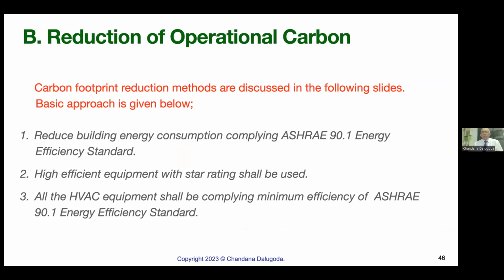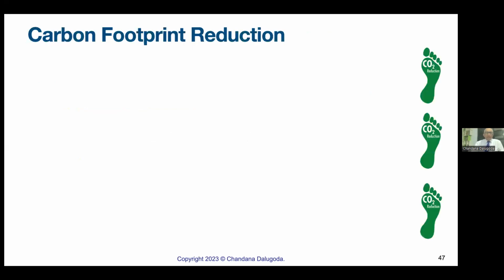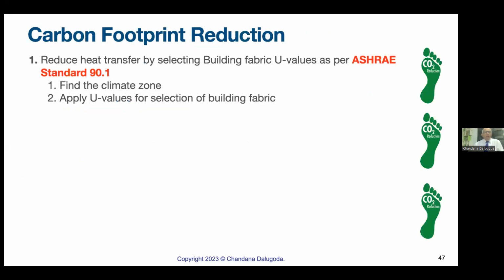So reducing carbon footprint, the methods, how do we do? How do we reduce 50% energy of a building? Quickly, we'll go through the actual steps. We'll have to find the climate zone of your country, and for that particular climate zone, the ASHRAE standard gives you thermal values, like for a brick wall, what should be the U factor? Stone wall, what would be the U factor? A cement hollow block, what would be the maximum U value?